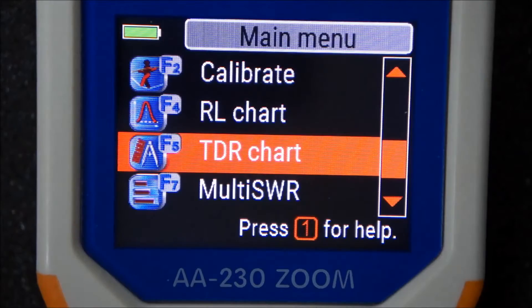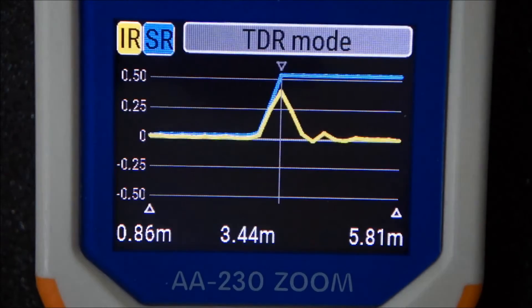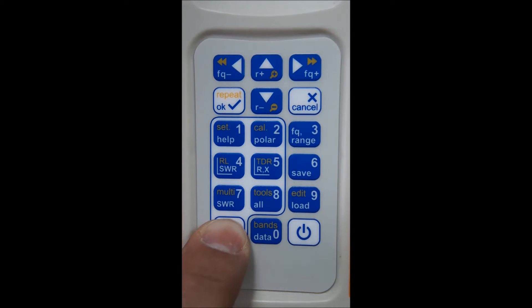For example, you can enter the TDR mode via the main menu using the cursor keys, or you can use the hotkey F plus 5 to enter the TDR mode directly.